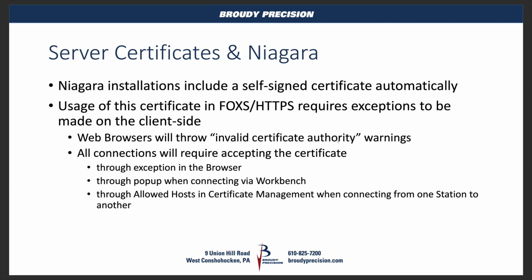So within Niagara, we get a self-signed certificate automatically with every install. And that certificate is used for our FOXS and HTTPS connections. But because it's self-signed, our web browsers and our Niagara installs don't know to explicitly trust that certificate when we go to connect, so we have to tell them to. You'll get an error, something along the lines of an invalid certificate authority from the browser, and you have to click through and accept that invalid certificate authority in order to access it.